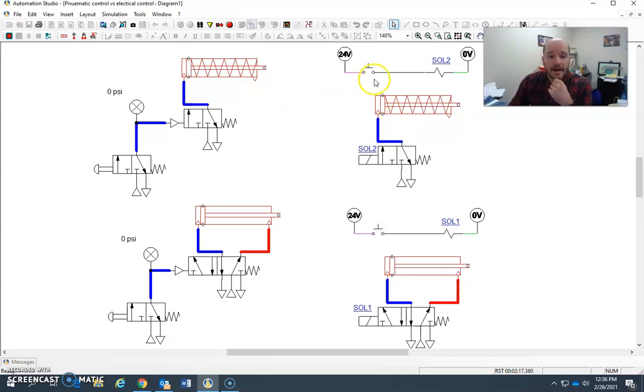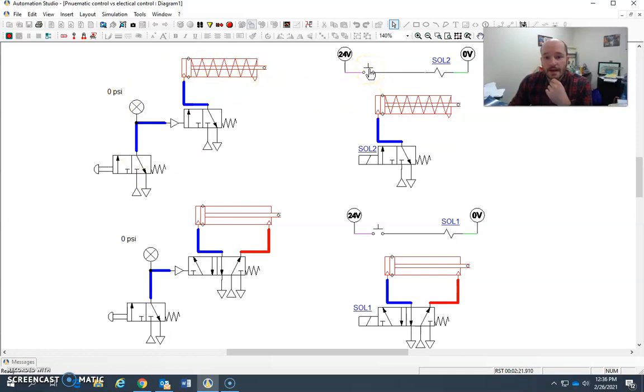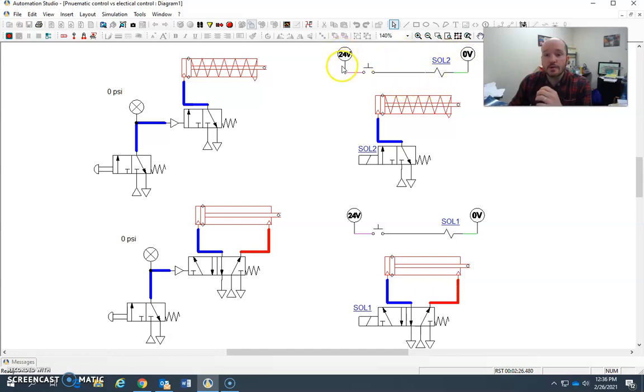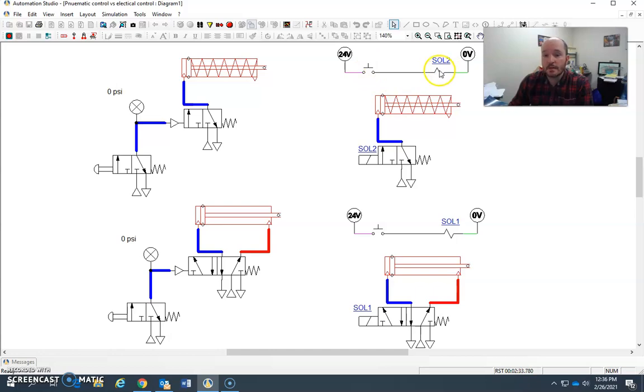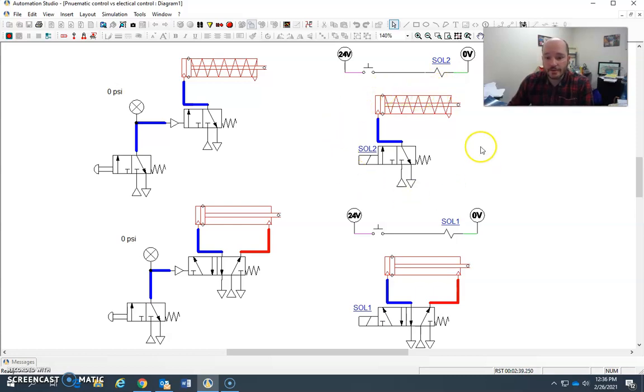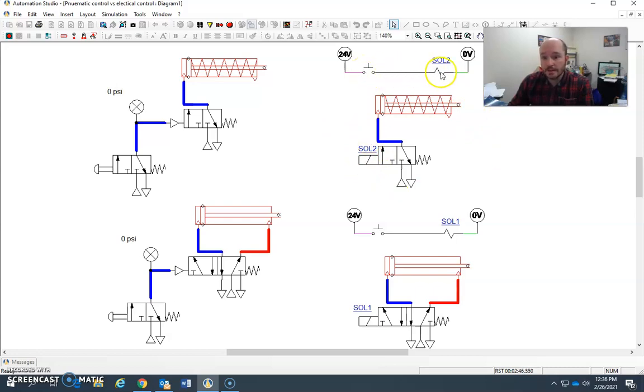Here I have the electro-pneumatic version of this one. I come over here, I activate the start button. This will engage the solenoid. This here is the electric control circuit. So when I push this, it's going to activate this. Solenoid 2 is represented by this symbol in the control circuit. In the power circuit, which is our pneumatic, it's represented by this symbol here. So when I come over here and I push this, it's going to engage this, which will activate this and shift the spool into its open position.